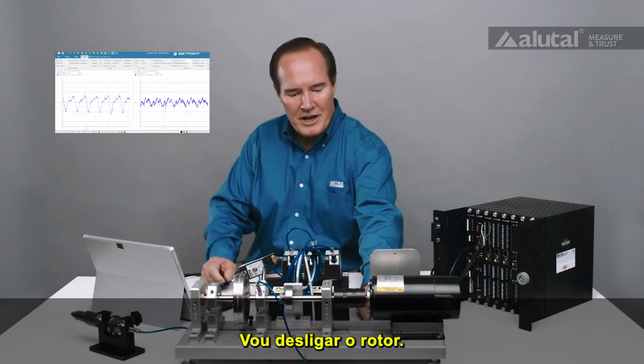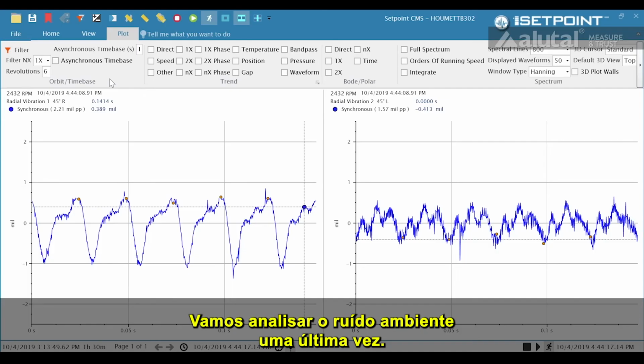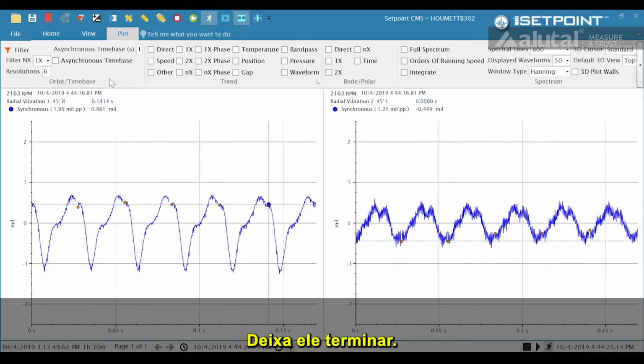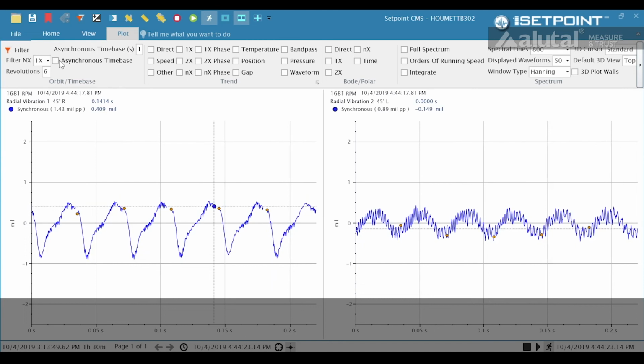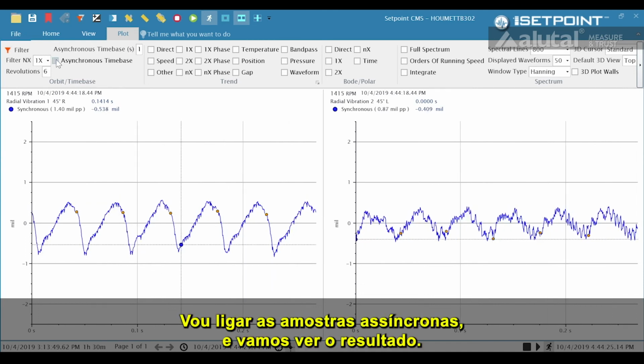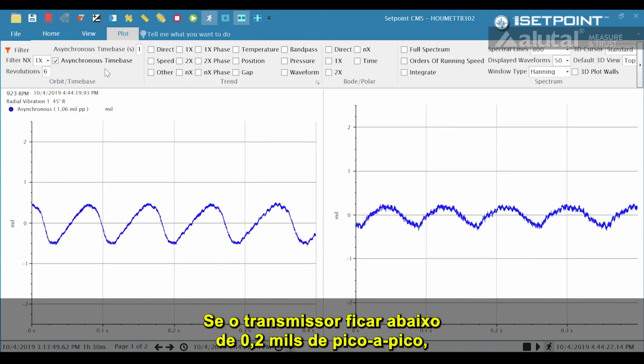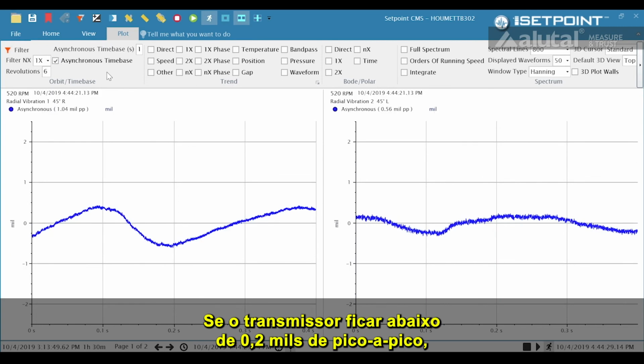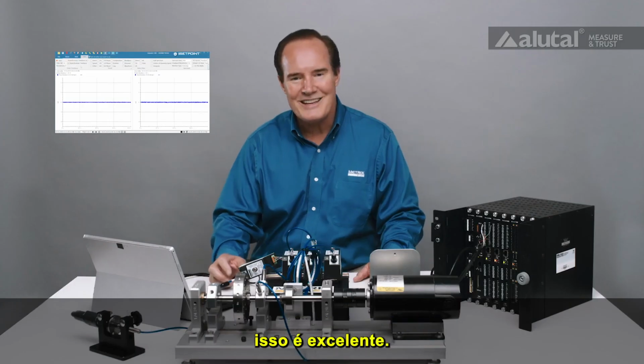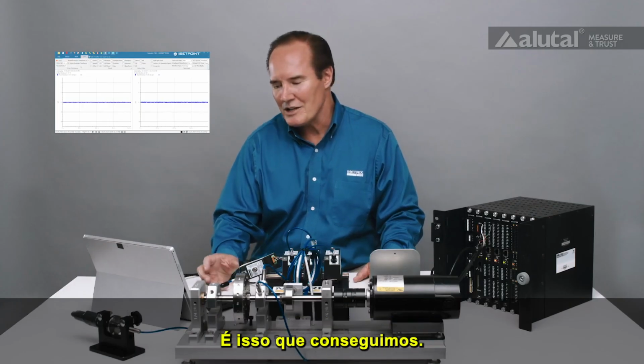Let me go ahead and shut down. We'll take a look at the ambient noise level one last time. We'll let it finish up. Let's bring up asynchronous and look at what it looks like. You know, with the transmitter, you're at less than 0.2 mils peak to peak. That's really excellent. And really that's where we're at, 0.14, 0.18.